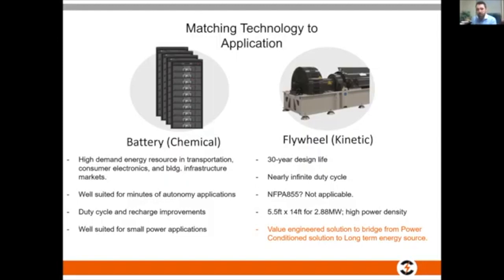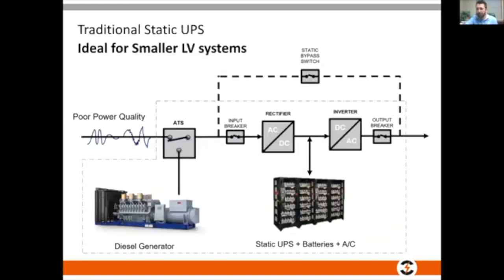And then, of course, the very last one, it's a value engineered solution. So it's a mechanical coupling. And that's why, for many who joined the presentation, you saw the title, which was, we mechanically integrate a UPS into a diesel generator. So it's a very compact, very simple design. Just to go a little deeper, and by the way, this is still very high level. My apologies for those in the audience who are used to looking at one lines in a much more detailed view. But just as on the face of it, we have a static UPS.